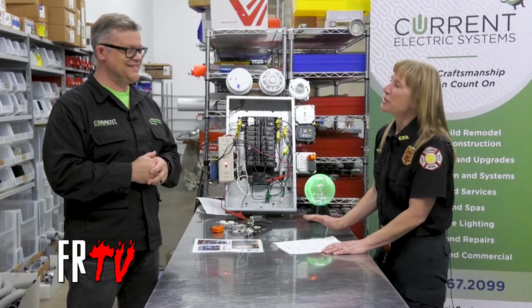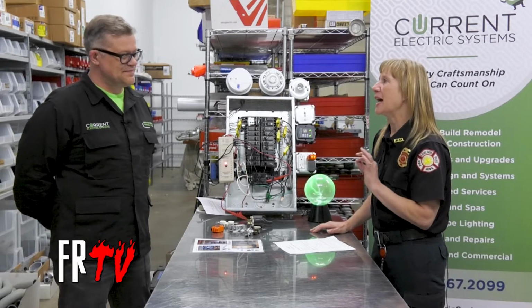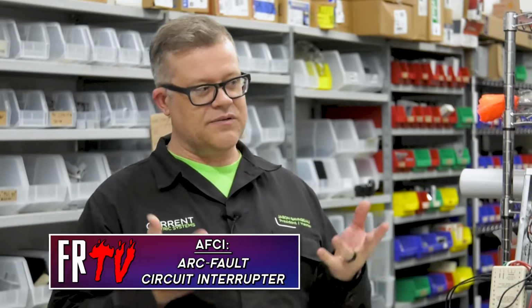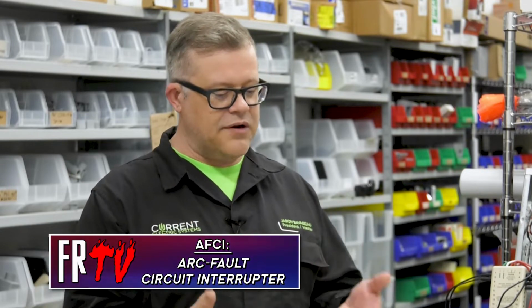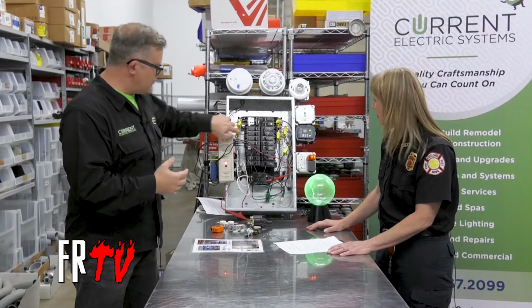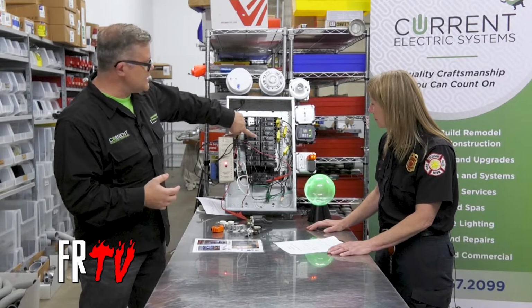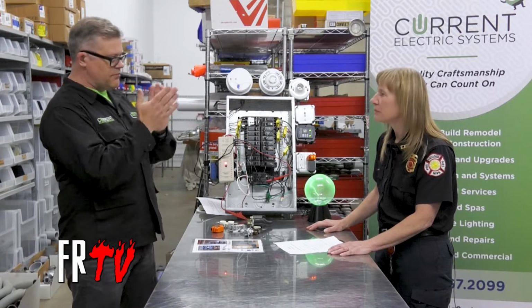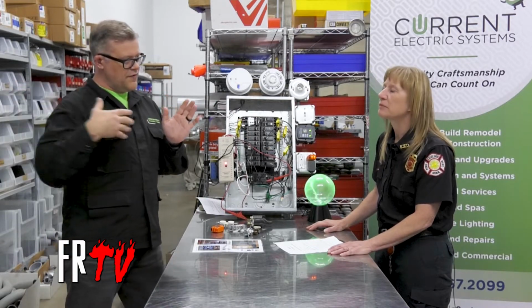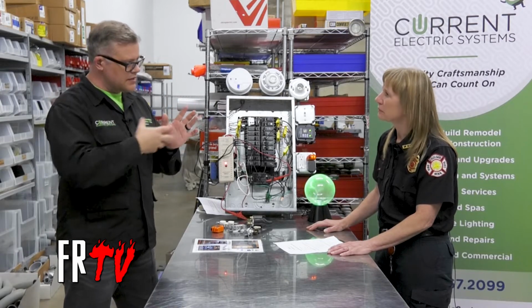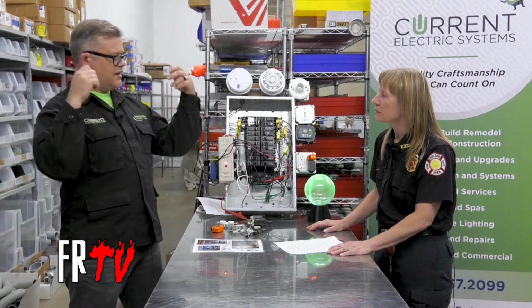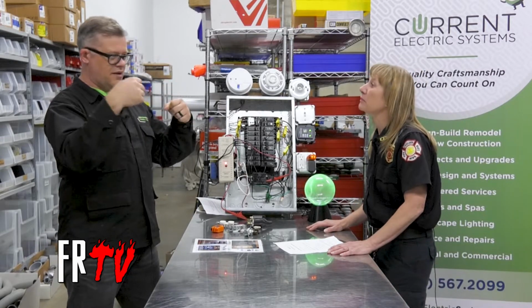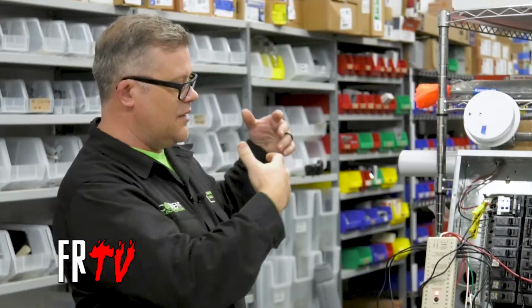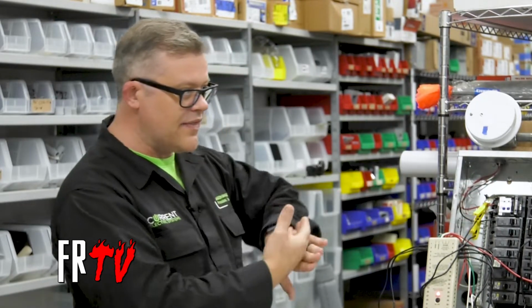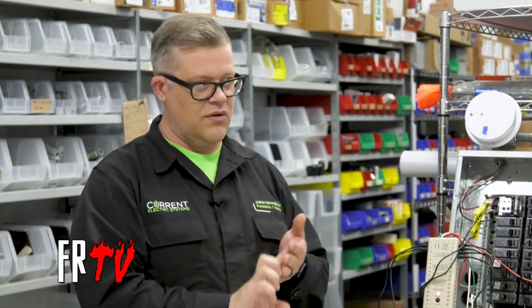Not a good idea. Can you tell our viewers the difference between an AFCI and a GFCI? So an AFCI is a relatively new technology, standing for Arc Fault Circuit Interrupter. A normal circuit breaker like this one, with 15 amps and a handle, breaks the circuit when there's more than 15 amps flowing, or if we get a short circuit where the wires connect directly and everything flows from the transformer. So it breaks on an overload, short circuit, or ground fault.